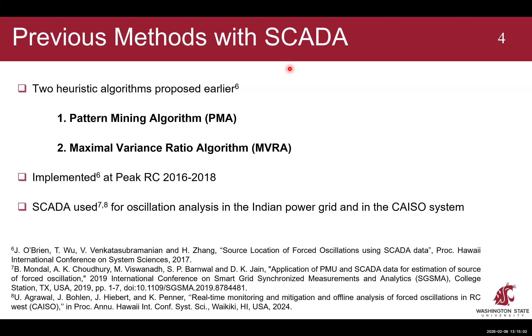We saw that the SCADA-based approach has been used in industry. There was a recent paper from the Indian Power Grid, and it was also reported by CAISO, California ISO, that they have used SCADA for oscillation analysis from IBRs, where PMUs were not available.